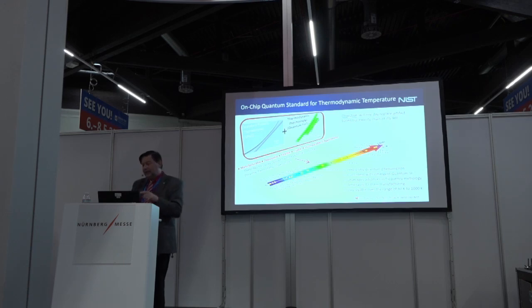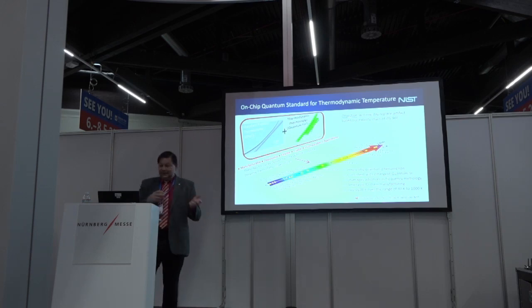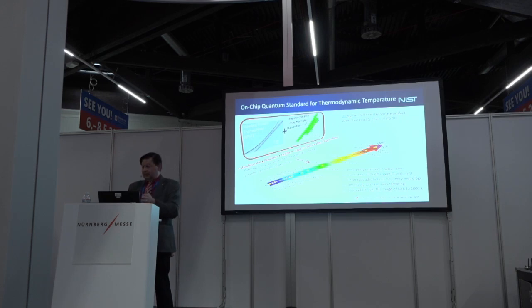check-in. What we like about this sensitive photonic thermometer, which we call SPOT, is that because it's made out of silicon and uses photons, it doesn't drift like the standard platinum resistance thermometer, or SPRT, which is made out of platinum wire, where the metal boundaries can kind of crystallize, and so the resistance can change. And if the resistance changes, it has to go back and get recalibrated. So what we like about SPOT is once it's characterized, when manufactured, it would never need recalibration again.